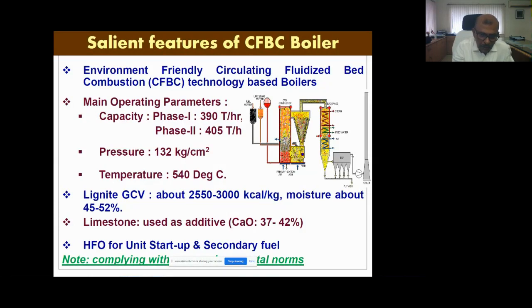Apart from lignite, we are using lime also as an additive, mainly to capture the sulfur present in this. That is the beauty of this CFBC technology. And more than 90%, rather 94%, of sulfur we capture at source. So this is very helpful for complying with the new environmental norms. And another factor: the temperature range is around 850 to 900 in the combustor. Basically, it is in the range of 850. So the heat transfer area is very large.